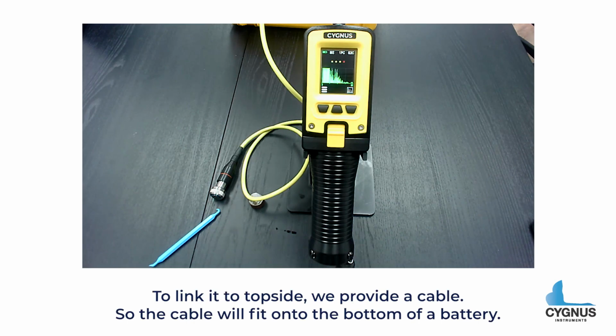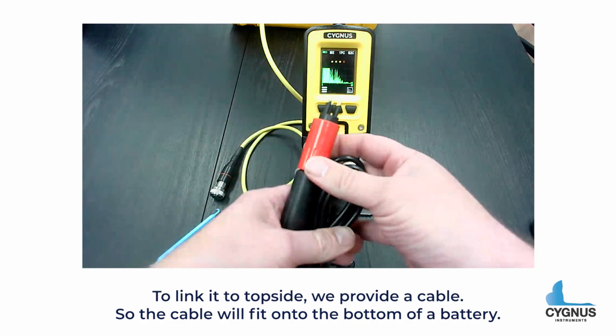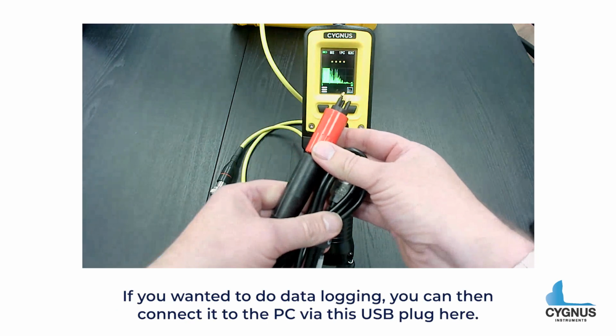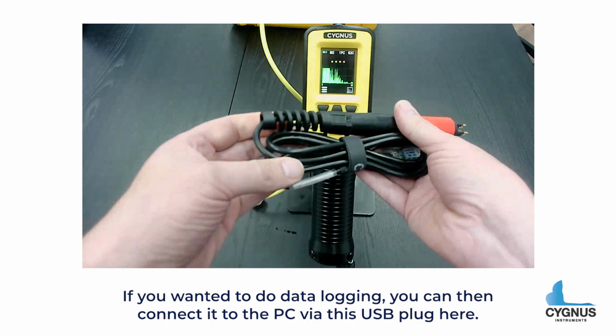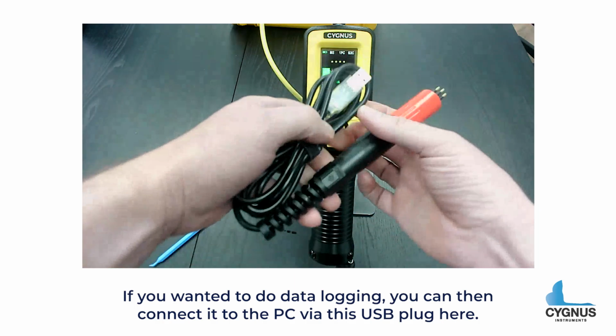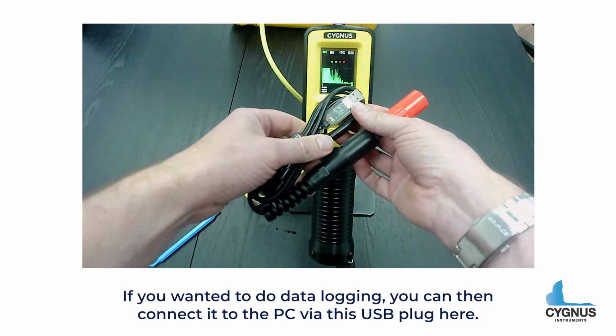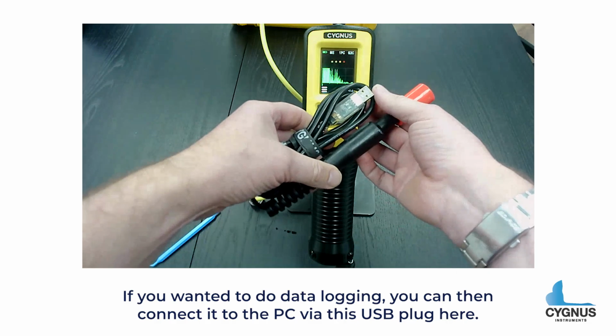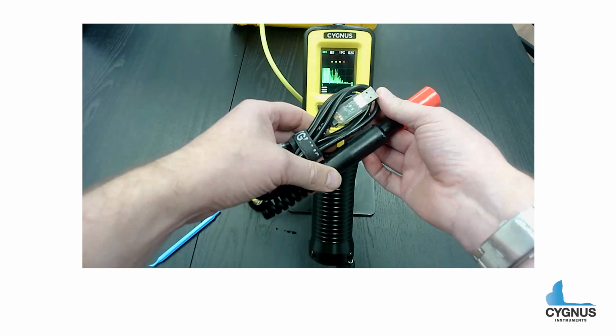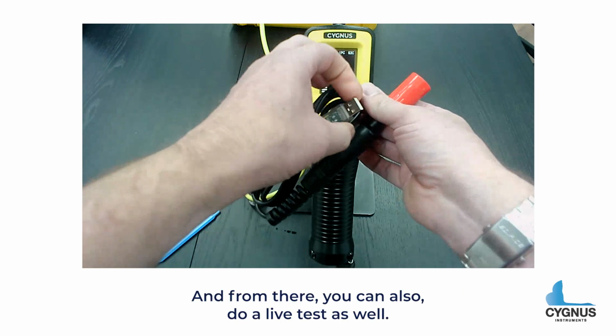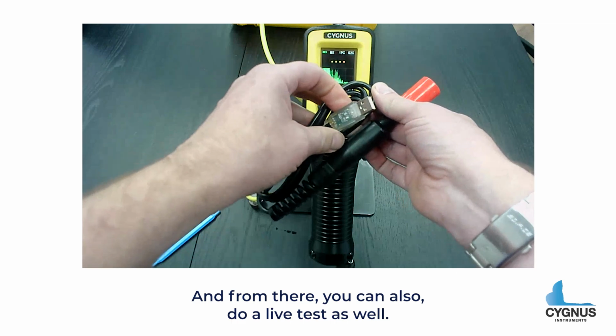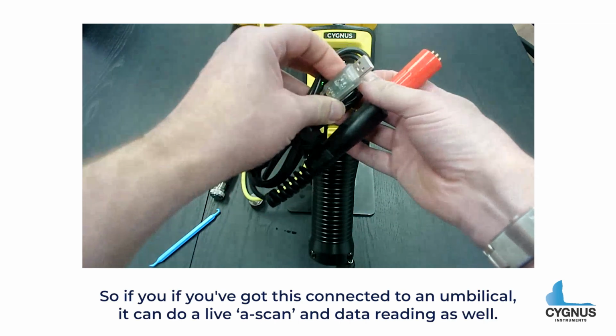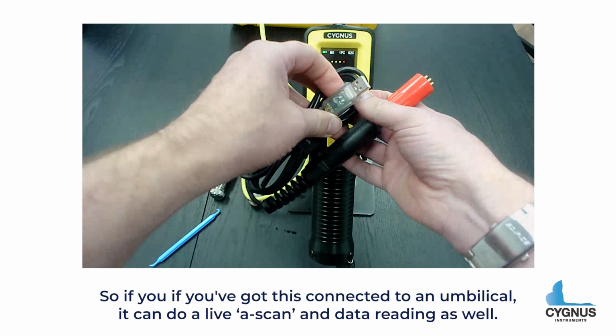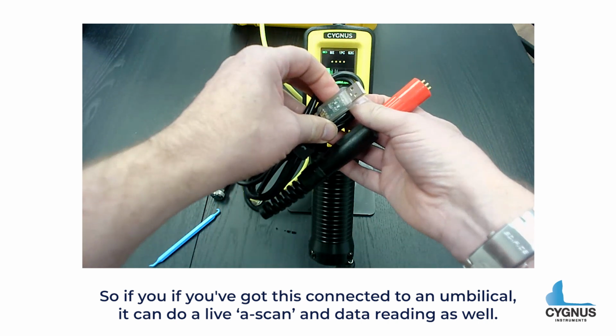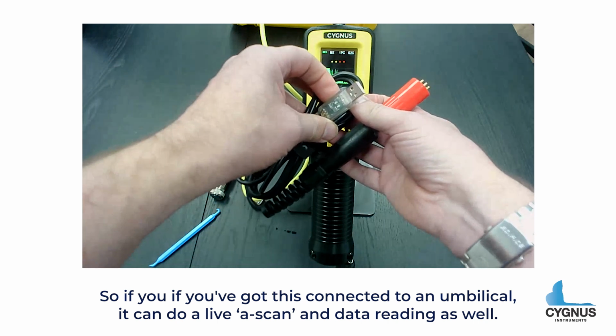To link it to topside, we provide a cable. The cable will fit onto the bottom of the battery. If you wanted to do data logging, then you can connect it to the PC via this USB plug here. And from there, you can also do a live test as well. So if you've got this connected to an umbilical, it can do a live A scan and data reading as well.